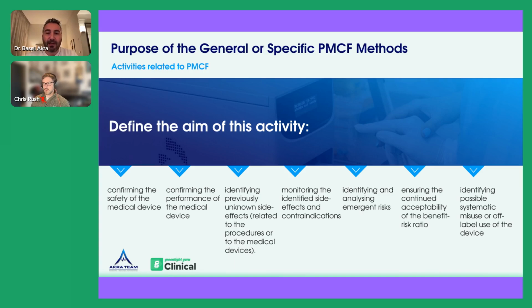You do that by getting 2 years, 3 years clinical data, and then you get to the market. But those patients will have that device for a longer term. Therefore, a post-market clinical follow-up is necessary. But then you need to define how long shall I follow the patient? And then you need to consider what the standard is telling me, what the state of the art is telling me.